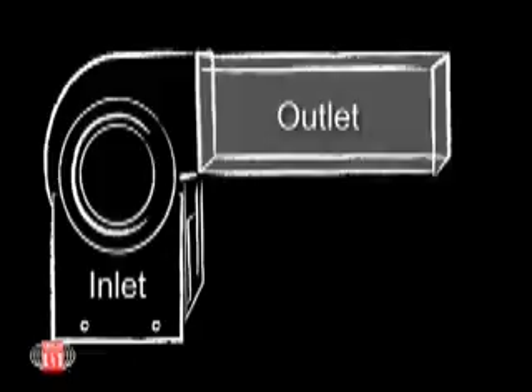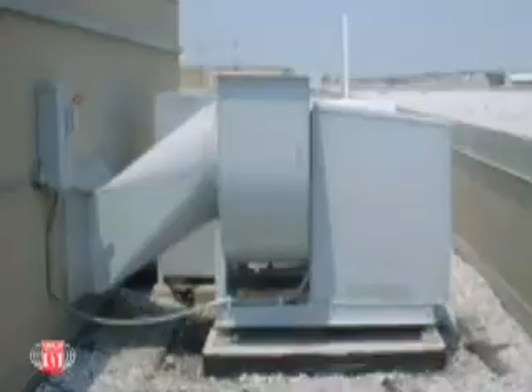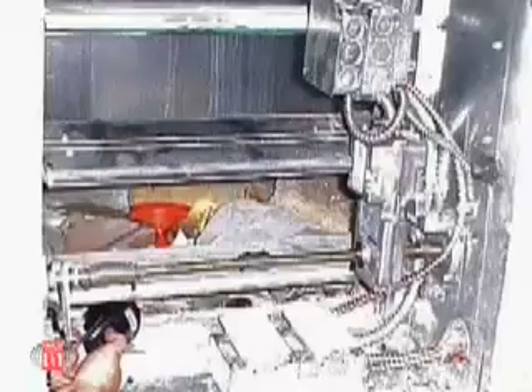System effect at the fan inlet and outlet seriously impacts airflow. The first major impact involves proper fan inlet design. As stated earlier, the airflow at the inlet must be fully developed, symmetrical, and free from swirl. Non-uniform inlet flow is the biggest cause of system loss. Factors adversely affecting inlet flow are insertion of obstructions, elbows and dampers too close to the fan inlet.